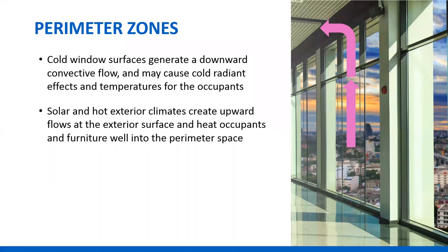When the sun is shining and the glass is tinted, the glass may get hot. If there's shading inside the window, the shades may get hot as the sun shines on them. In either case, hot air rises. We have talked in the past about recommending a return slot to the return air plenum above the window — they've been doing that in Houston for some time. It's a good way of taking heat away from the space without the HVAC system having to handle it in the space.